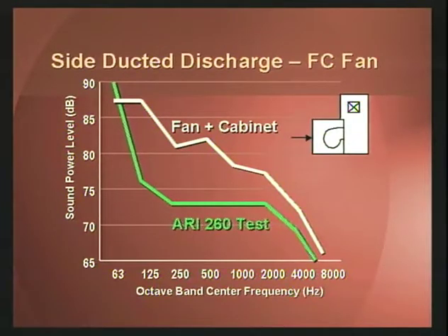The prediction in white is the fan plus cabinet effect using an AMCA 300 test for the fan sound power, coupling to that a prediction using classical equations. As you can see in this case, depending on the octave band, there can be as much as 10 dB difference between the 260 tested data and the predicted data. Obviously, using a prediction method other than ARI-260P makes it necessary for us to put in factors of safety in our calculations when we're doing application predictions to prevent errors in our application sound levels.